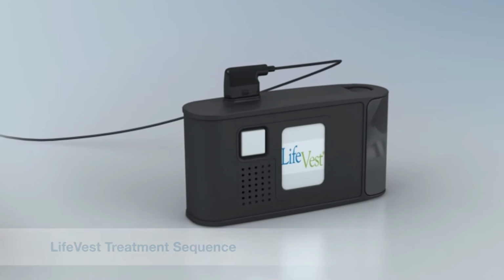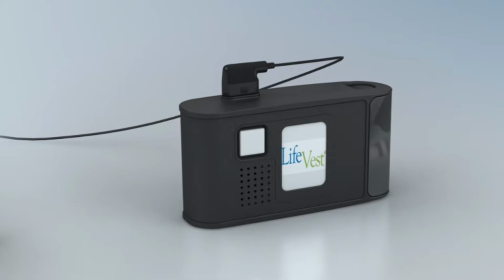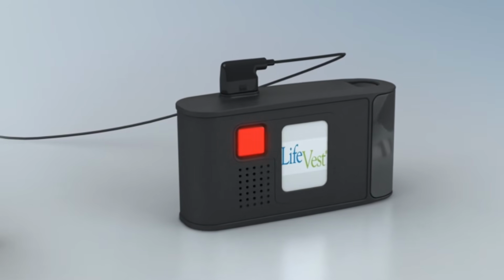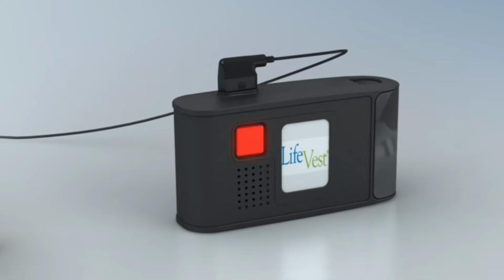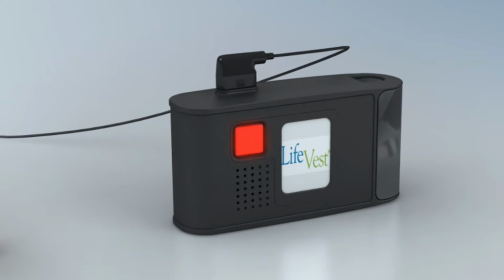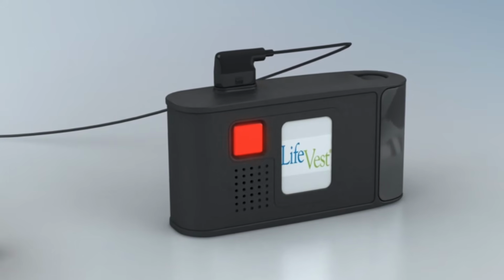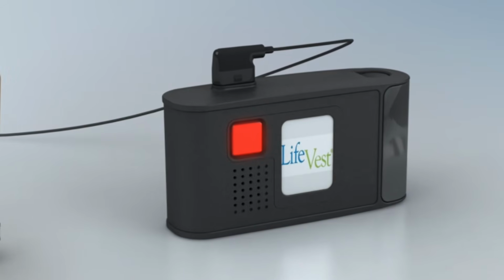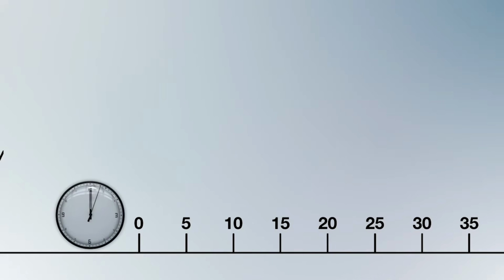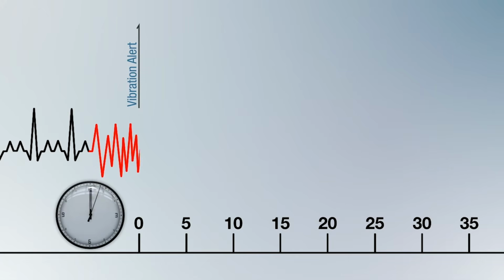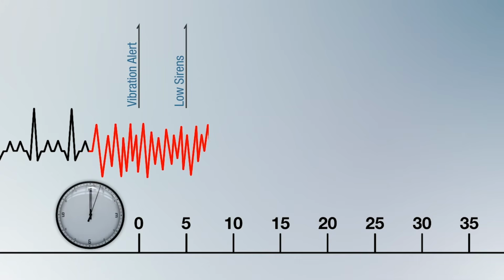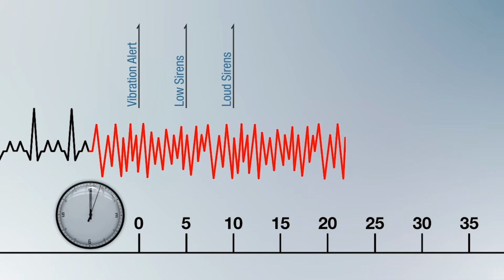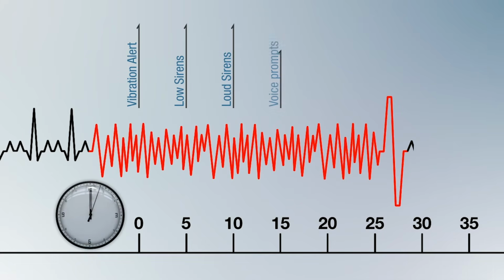During this time, if the patient is conscious, they are instructed to press and hold the response buttons, which are found in the top corner of the LifeVest monitor. The response buttons prevent a treatment shock from being delivered. Please note that only the patient should press the response buttons. If, however, the patient is unconscious, the sequence will run through a 5-second vibration alert, followed by a low single-tone siren, which is broadcast for 5 seconds, followed by 5 seconds of loud 2-tone sirens. The device then transitions to voice prompts accompanying the 2-tone siren.